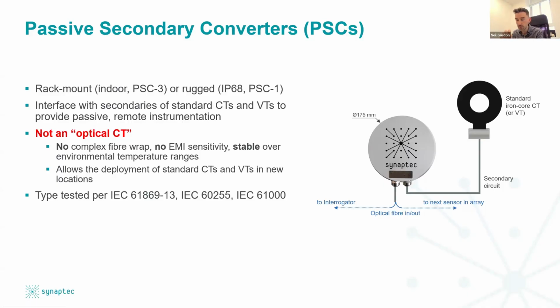So each PSC at a given location will splice into the existing optical fiber coming down from the OPGW into the cable, for instance, at any convenient local access point. So at a fiber optic splice box, which is typically nearby. And that splicing operation on single mode fiber is a bog standard telecoms operation. It's very quick and simple for a telecoms engineer to do. It takes moments, a few seconds really. So each PSC is installed in series down that fiber. They're daisy chained down the entire length of our sensor array. And the full PSC suite of products is also type tested to IEC 61869 and the various EMC, vibration, and environmental requirements, just like any other measurement technology in the sector.